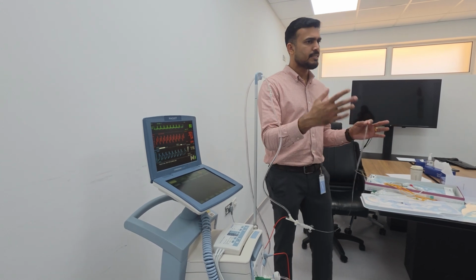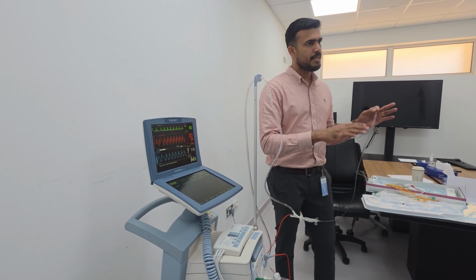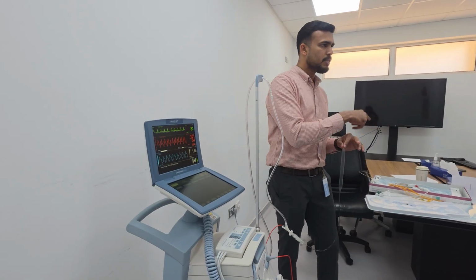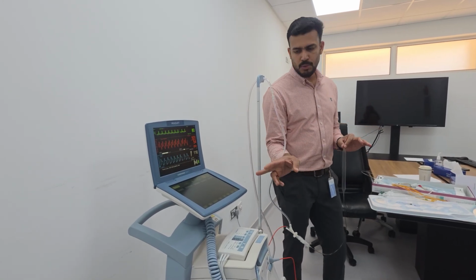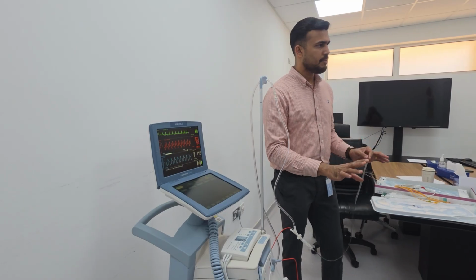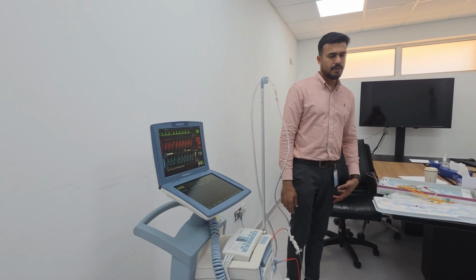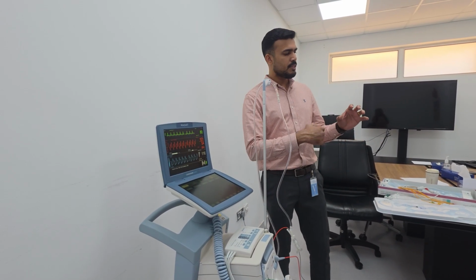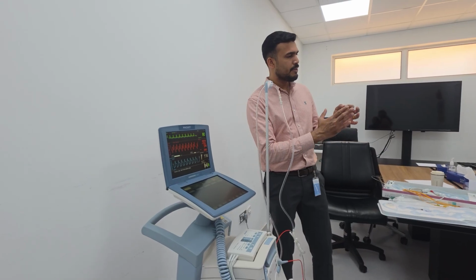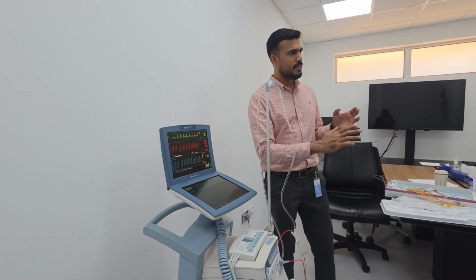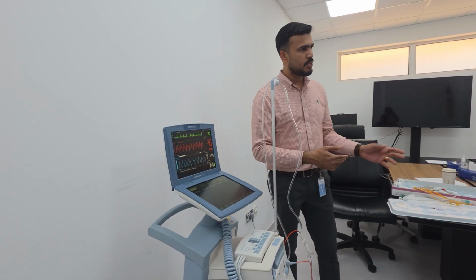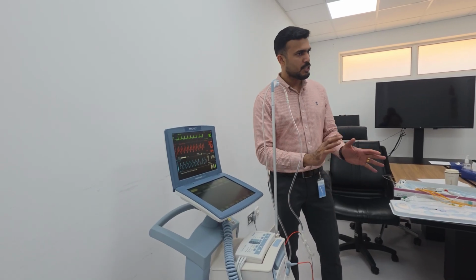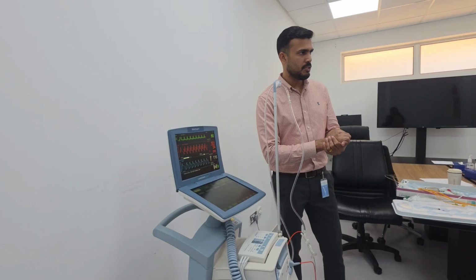So if you are getting a continuous leakage alarm, there is no leakage, and you did proper troubleshooting, then you can go to the patient temperature. If it is high, just do a manual filling once an hour. Then the alarm will go. Yeah, automatically. Okay. Because in 1 hour, because of the temperature differences, there should be a slight diffusion to the patient side. So every 1 hour maybe the machine will give you an alarm. To avoid this, you can do a manual autofill. But make sure that this is only because of the patient's high temperature.